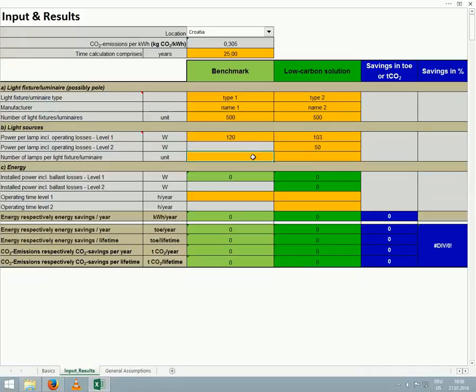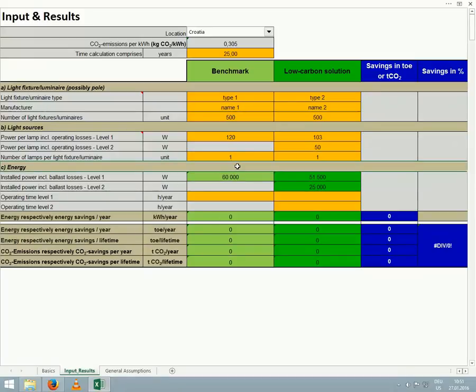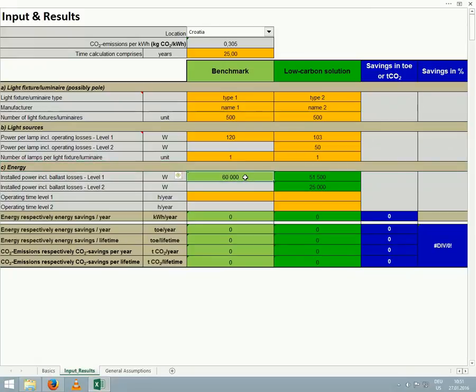Then, we must enter the number of lamps per fixture, and in our example, we enter 1 for both models. Once we have entered all of this information, we can see that the installed power base in watts is provided for us by the calculator. It is the product of number of light fixtures multiplied by power per lamp, and then by lamps per light fixture.